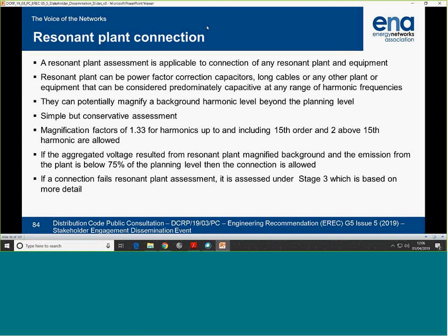I'm trying to get some power factor correction in this document. When would installing power factor correction apply, is it when you apply for a new network connection, or is it significant changes, or there's obviously power factor corrections going in on a daily basis on site? Absolutely right. So basically, this section says, if you are putting in power factor correction capacitors, you need to be mindful of harmonics. That's basically what it says. And when you have the rating for the capacitor bank, then you need to put it into those equations in the document. And if you come up with these numbers, or better than these numbers, then you're fine. You can connect your capacitor. But if the numbers you calculate are higher than these, then you need to go to the DNO and ask for more information.